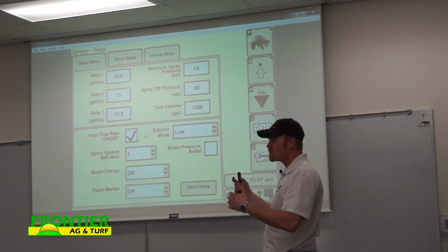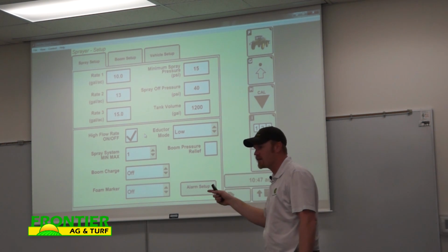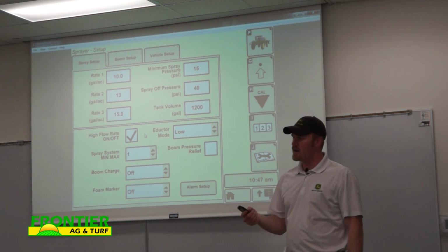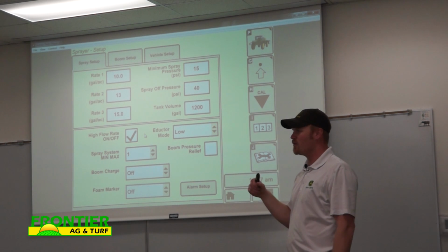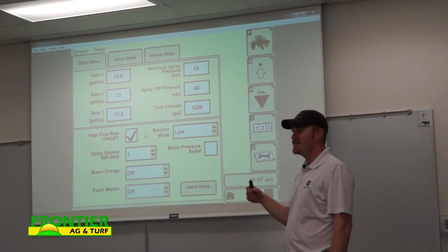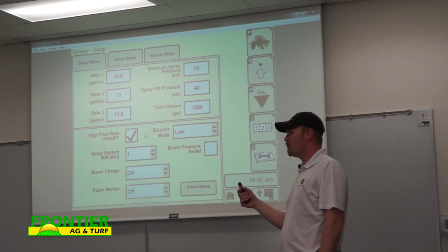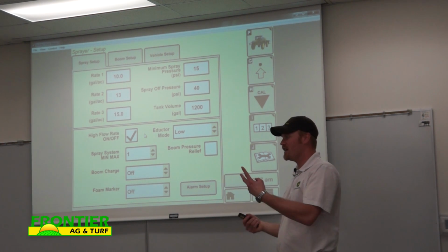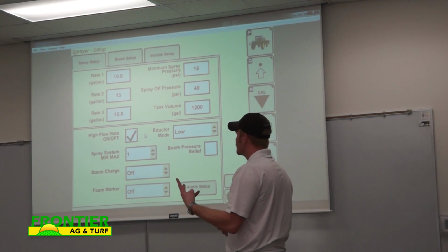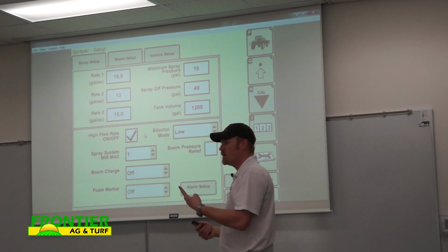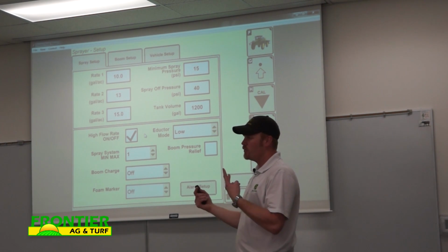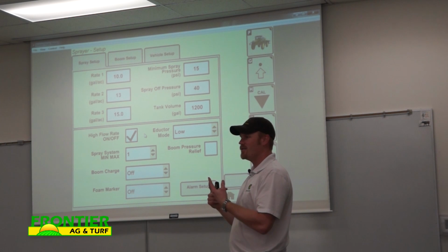Okay. There's no electronic thing, so if the box is checked and you're trying to put out a rate, but the valve is closed, what's your rate actually doing? It's half of what it should be, right? Because you're taking a calculation of 2 flow meters. So if you're taking 2 flow meters and you're only running fluid through one of them, the other one's reading 0, it's going to take half of what it is.